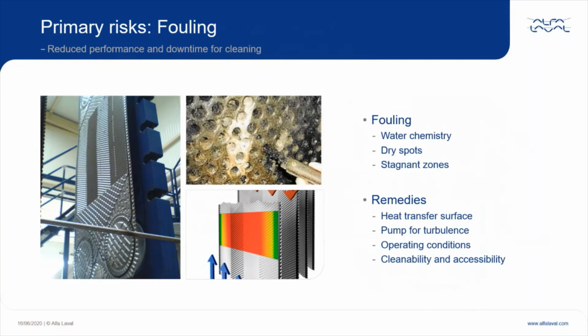The lower solids accumulation or fouling on the heat exchanger surfaces, the longer the runtime between cleaning cycles will be, and this will give a higher availability of the system and also help to reduce the total consumption of cleaning chemicals. During the cleaning cycle, which is typically by circulating a chemical cleaning agent inside the system using the recirculation pump, the higher turbulence and shear forces on the heat transfer surface will also be helpful, and the plate and frame heat exchangers can, in addition to this, also easily be opened up for inspection after finalized cleaning and, if necessary, be cleaned mechanically.